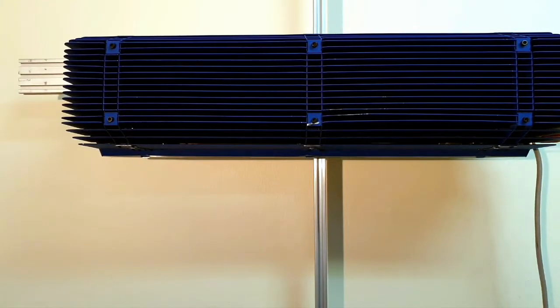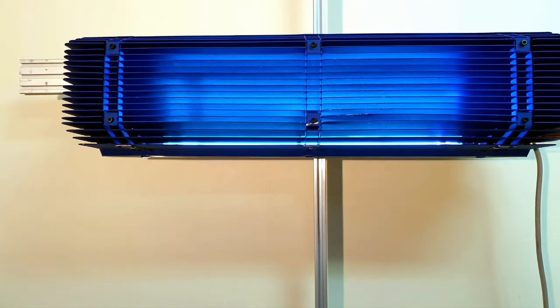So with the unit back together, you just want to give it a quick check, switch it on, make sure that it works, and then we'll move on to the second set of post-cleaning performance measurements. So we've taken the device apart, replaced the components that need to be replaced, lamps, ballasts, etc. Put it back together and switched it on. It seems to be still working. We still need to do the final performance measurements, but don't get too excited yet.